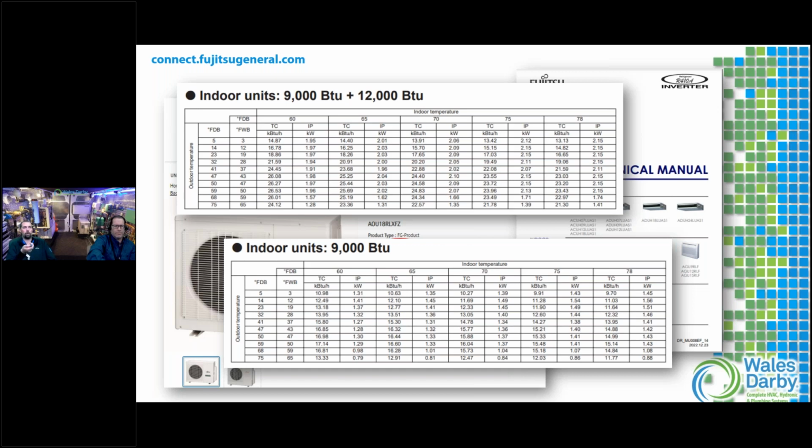And if I go a little further here on that same 70, that 10.27 is really a 5-degree day, not a 14. I messed up there. It's 11.7 on a 14. We're at 10,000 BTUs out of a 9, right? This is where I think we see it a lot: maybe you would have picked a 12 or an 18 for this application. Sure. We could do it with a 9, and possibly even a 7 if we pulled up the 7 chart, depending on that room calc from the Manual J or the load calculator itself.